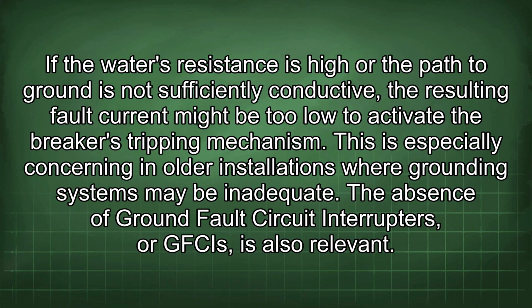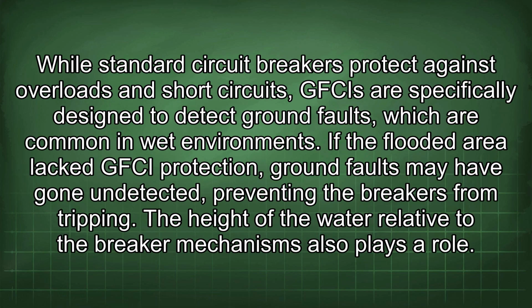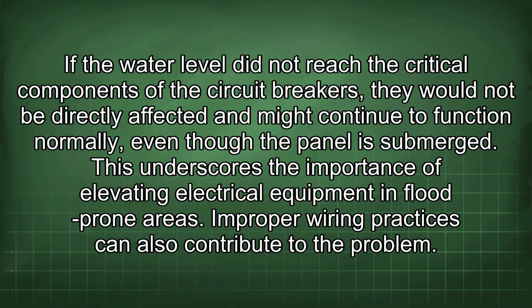The absence of ground fault circuit interrupters, or GFCIs, is also relevant. While standard circuit breakers protect against overloads and short circuits, GFCIs are specifically designed to detect ground faults, which are common in wet environments. If the flooded area lacked GFCI protection, ground faults may have gone undetected, preventing the breakers from tripping. The height of the water relative to the breaker mechanisms also plays a role. If the water level did not reach the critical components of the circuit breakers, they would not be directly affected and might continue to function normally, even though the panel is submerged. This underscores the importance of elevating electrical equipment in flood-prone areas.